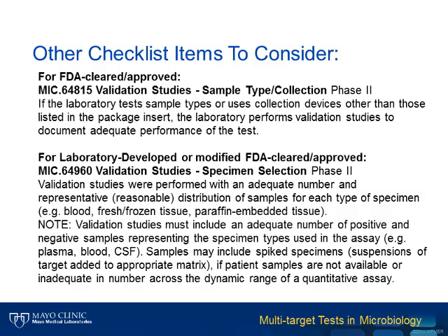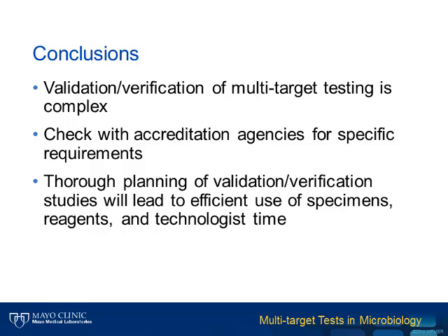Finally, if the laboratory validates specimen collection devices or sources that are different than the package insert, the laboratory must perform validation studies to document adequate performance of the test. The details are up to the lab director, but it is important to make sure that the lab has confidence in the results they are reporting out. For laboratory-developed or modified FDA-cleared or approved assays, laboratories must be sure to validate each source that will be used in the assay. This may include spiked specimens, but it is important to perform complete validation for these sources to ensure that performance characteristics are as expected.